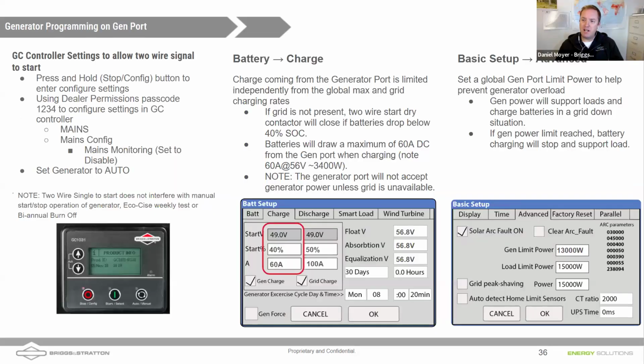Now, Nathan, I know we only have about 9 minutes left, but one thing you are going to have to do with our generators is that the generators, ours at least, are constantly receiving voltage and current from the grid. That's to keep the starting battery inside the generator charged and keep any cold weather kits on in the battery. Additionally, the generator is looking at that grid sense to determine whether or not it should start itself up or shut itself off. They come from the factory programmed this way, right? Yep. And so if it's receiving power like it would if you had a Sol-Ark there, even in a grid down situation, it's not going to start.